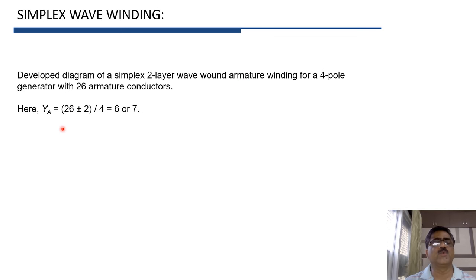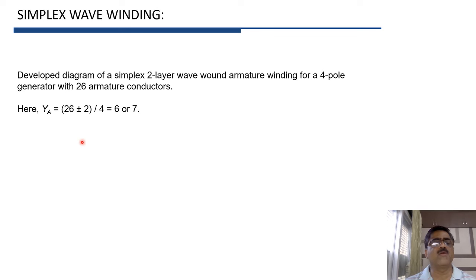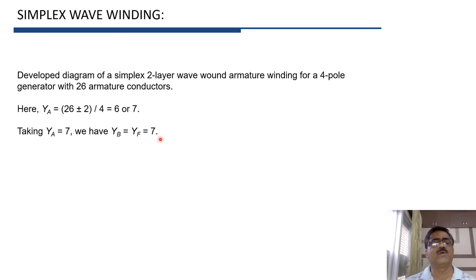YA = (Z ± 2) / P = (26 ± 2) / 4, so YA is either 6 or 7. Since YA is an integer, the winding is possible. We have to select the values of YB and YF — they must be odd and can be equal or differ by 2. We will take YA = 7 with YB = YF = 7, and prepare the winding table with these values.